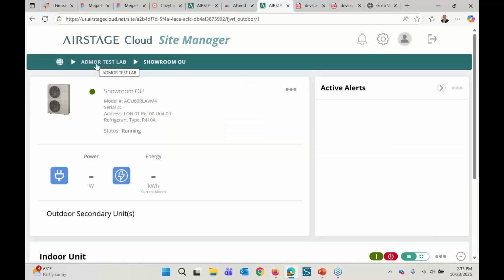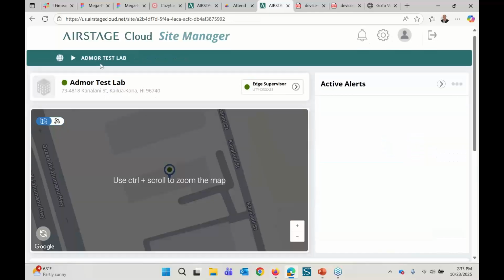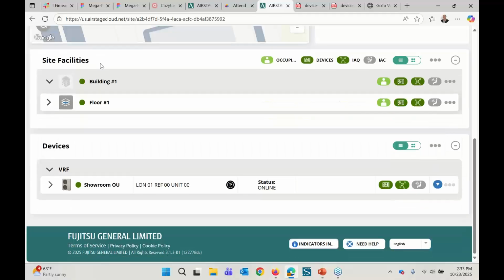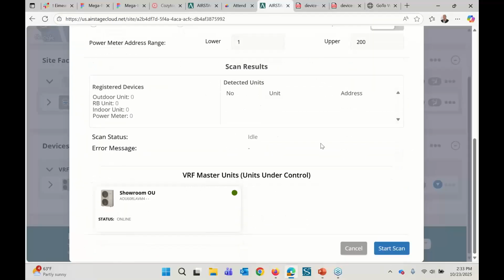Just a couple other quick service related things before we talk about the site manager. We talked about how you make things easy during startup and how you detect wiring issues and service issues. When your site comes online, this device container is going to be empty. What you do is come over to this button and run a VRF scan. That scan goes out on the network and asks what systems are installed.